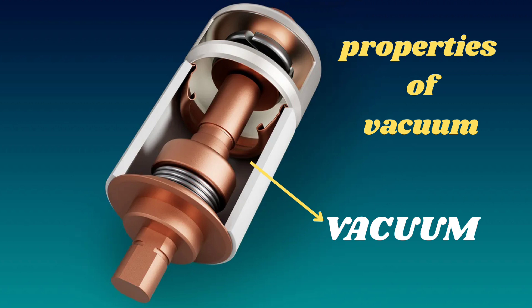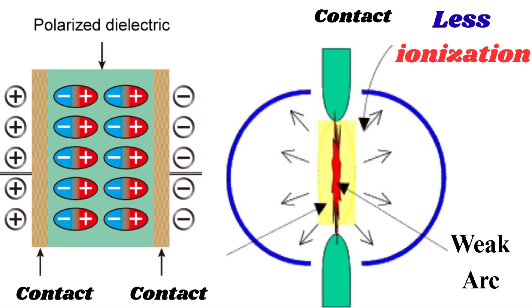Since a vacuum has no particles, including gases, and has extremely reduced pressure, the ionization of the medium is minimized, which reduces the likelihood of arc re-ignition. This unique property ensures reliable current interruption and increased dielectric strength. The vacuum environment provides high dielectric strength, allowing vacuum circuit breakers to withstand high voltages without breaking down. This is the unique property of vacuum that makes it a good arc quenching medium for circuit breakers.